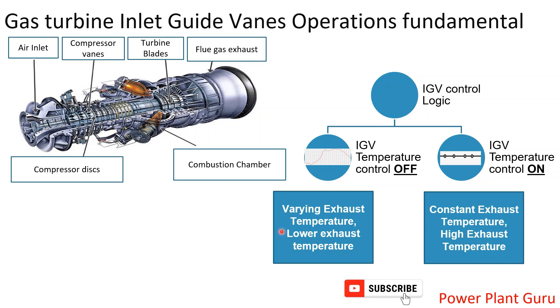If you are running an HRSG which generates steam using gas turbine exhaust gases, then you must operate the gas turbine in IGV temperature control mode ON. This is because in this mode, the IGV follows load and accordingly varies its position to maintain the exhaust temperature at the highest possible level.